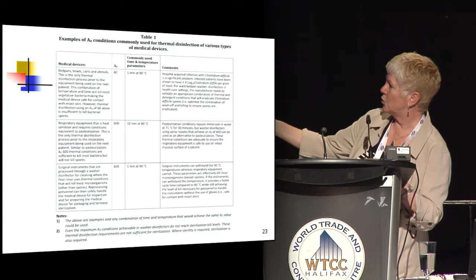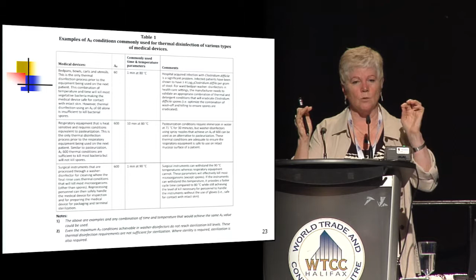If you look at an A sub naught of 600, this is 10 minutes at 80 degrees. This is the type of A sub naught you need for either your pasteurizers, or if you're using an automated washer for respiratory equipment and you want to achieve at least equivalent to a pasteurizer, that's the type of A sub naught that you need to get. And the way you get it, you can do 10 minutes at 80 degrees, you could do 1 minute at 90 degrees. So you can see the A sub naught is just telling you at a lower temperature you can get the same killing effect that you can get at a higher temperature, providing at the lower temperature you extend the time of exposure.